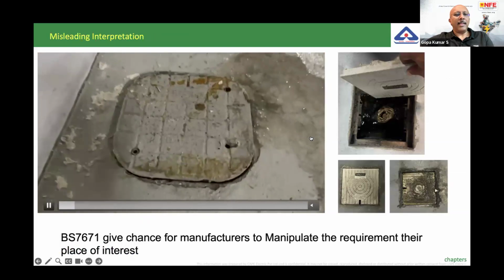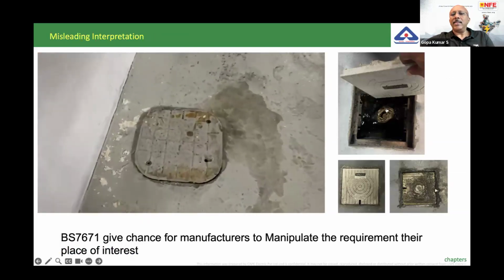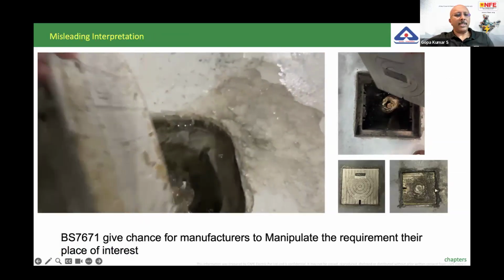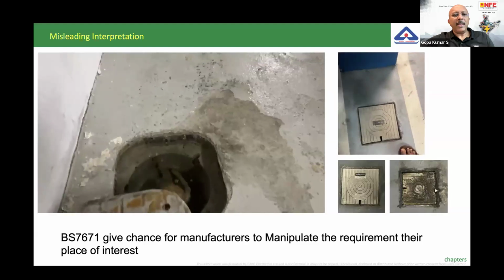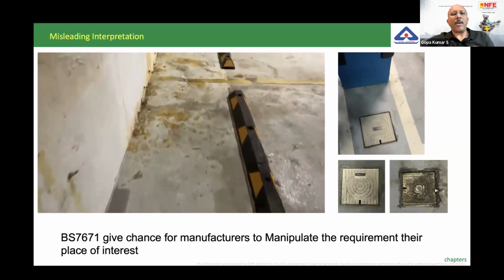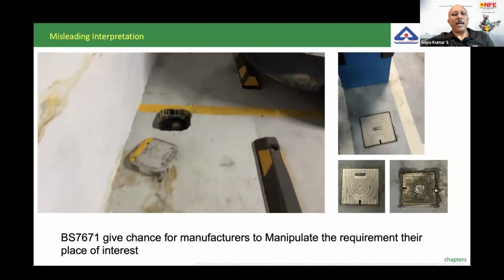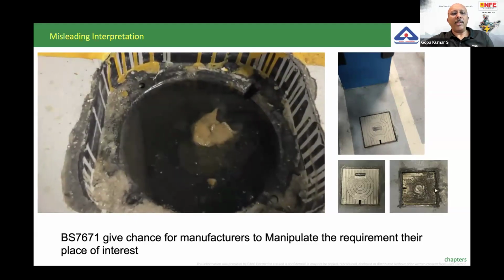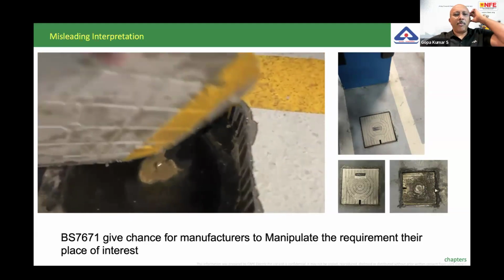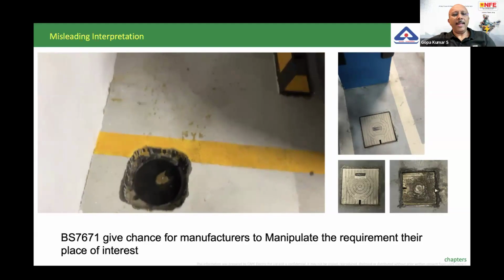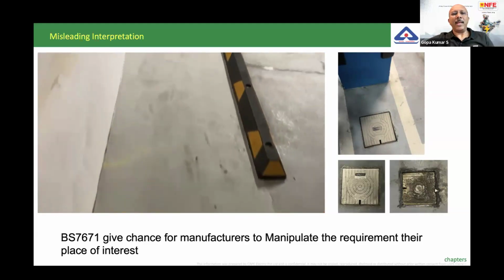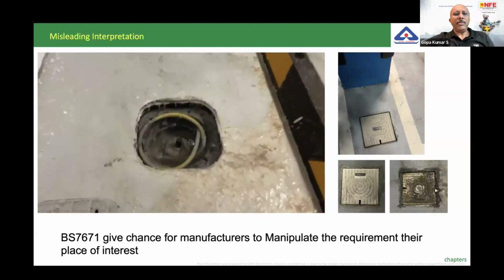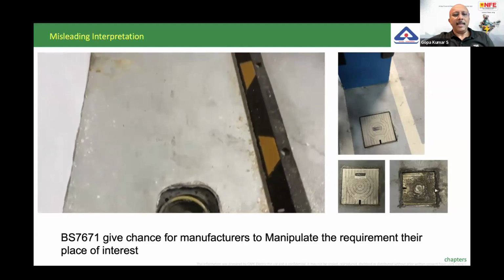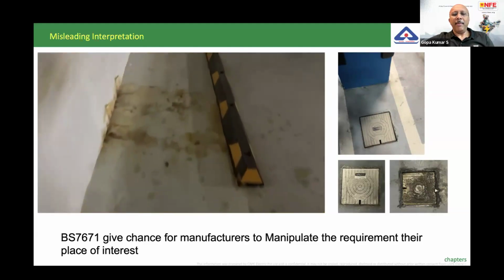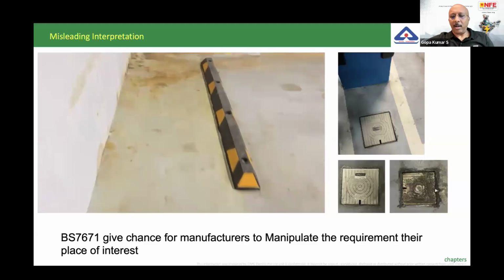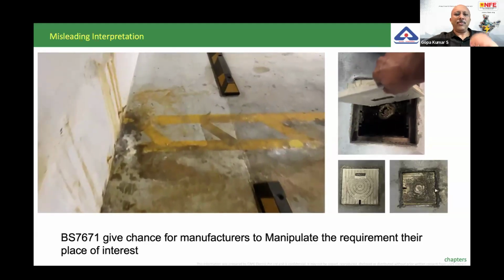What I am showing you in the video is electrical installations used in some countries which follow the British standard. So they always think that earth electrode means the vertical rod electrode in the soil. As a result, they put vertical electrodes on the foundation of the building, piercing through the waterproof membrane, which creates a much bigger problem of water leakage in future. Maybe after 10-15 years, the entire structure is in trouble. So I would say sometimes the changes from the IEC standards give scope for the manufacturers to manipulate the system according to their requirement, according to their place of interest. So it is highly dangerous.